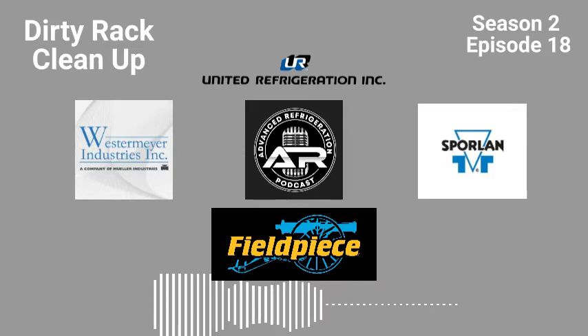Yeah, absolutely. I'd rather have expansion valves with the strainers in there any day. That's why I don't understand why all the electronic valves aren't required to have strainers. Sporlan has the EV with the strainer, and I've seen less fail than the straight-through valves with the internal strainer. The difference is they just have one extra S on there.